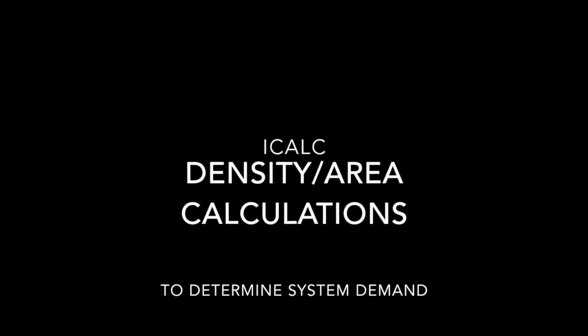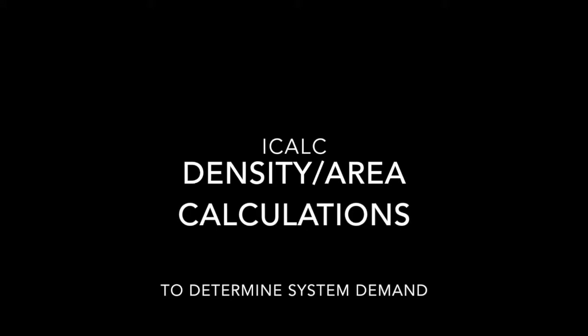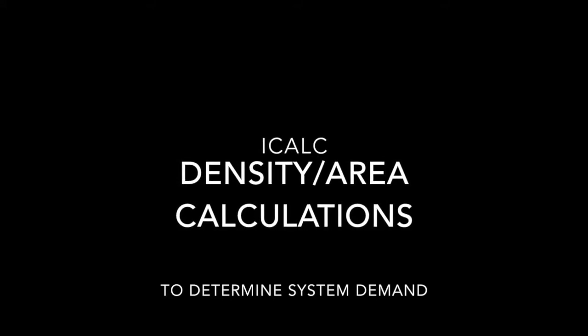This applet is for determining the required density and required area of sprinkler operation in a system design according to the density area method of section 11.2.3.2 in NFPA 13. It helps you check for adjustments and exceptions and places your design requirements on a curve corresponding to your occupancy classification. The first thing we want to do is open up our density curve page on iCalc.